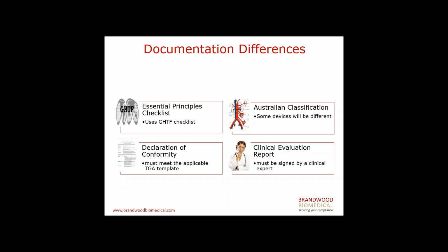And lastly, it's the clinical evaluation report. In Australia, it is a requirement that the report be written or at least endorsed by a clinical expert. As opposed to this, we have also noticed, just in our experience when handling these applications, that TGA is quite picky about the presentation of their clinical evidence report.